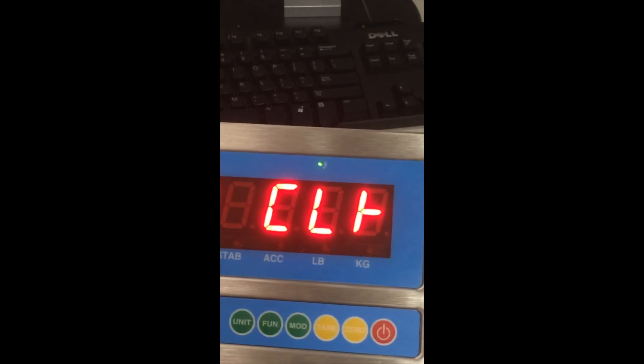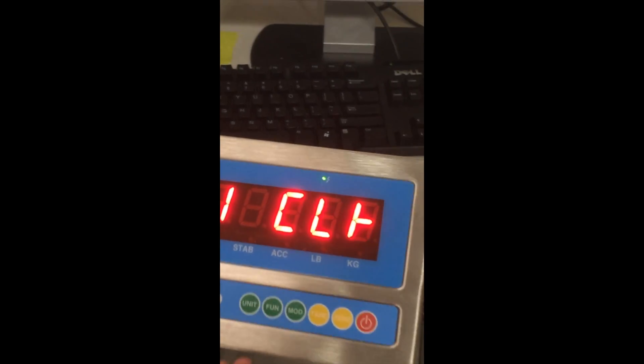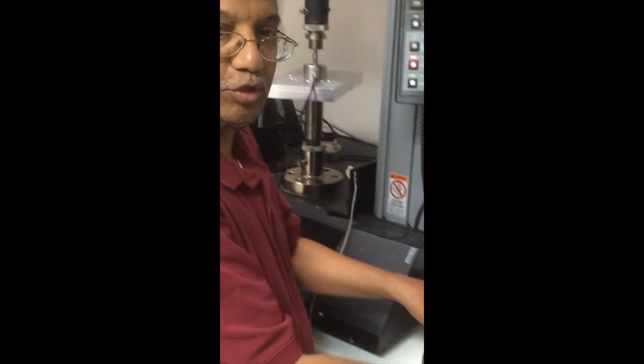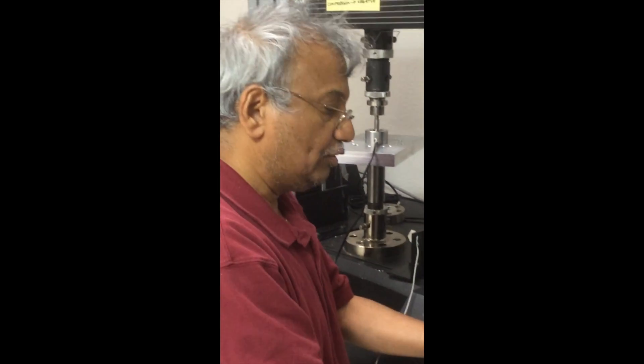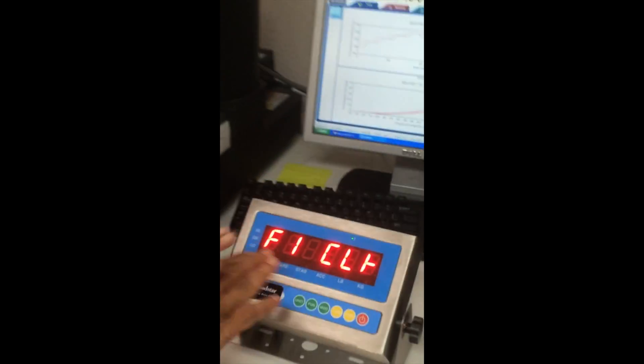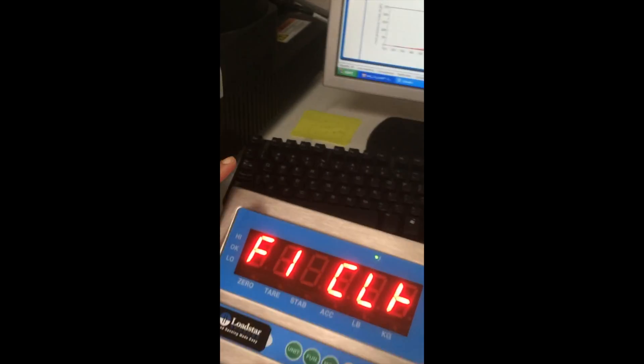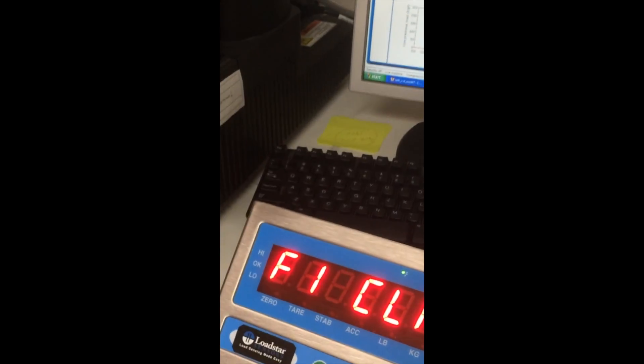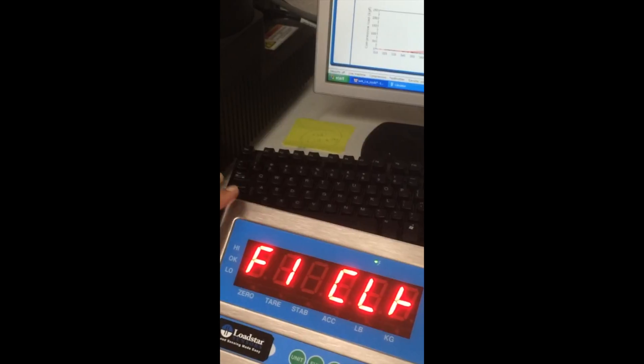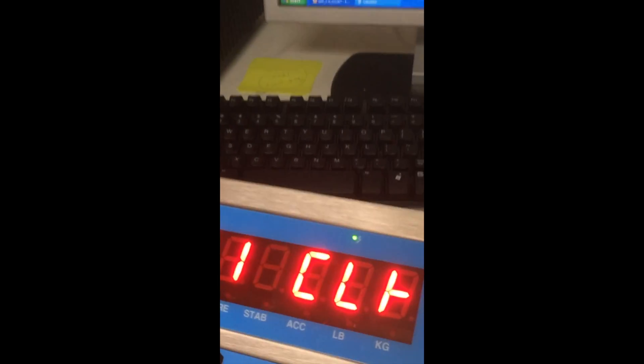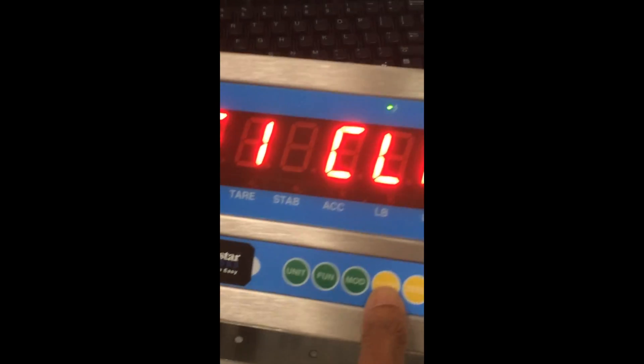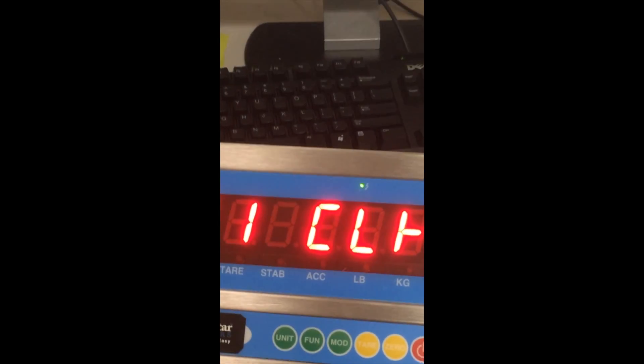So as soon as you power it up and go into this mode, this is the menu mode, you will see F1 for clock. Most of these commands you can ignore. We are going to concentrate on two commands. First we need to set the units. This unit can only be calibrated in kilograms.